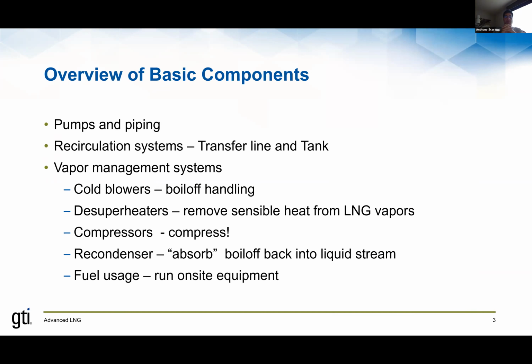This is an overview of the basic components in an LNG facility. So there's pumps, there's piping systems, there are recirculation systems. So LNG, as you know, is cold. The piping systems that it's in, if you don't have flow in those piping systems, over time, the heat penetrating into those piping systems will cause the LNG to warm up, cause it to vaporize, and eventually you could actually warm up that piping. So there's the systems in LNG piping systems. Some of them have a continuous recirculation of LNG through those systems to maintain them in a cold state.